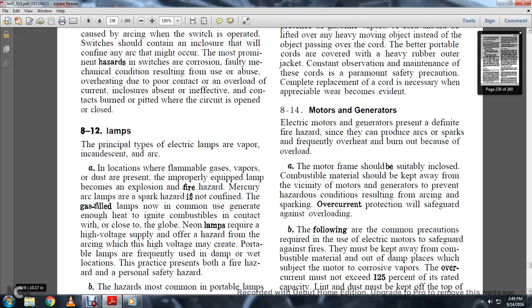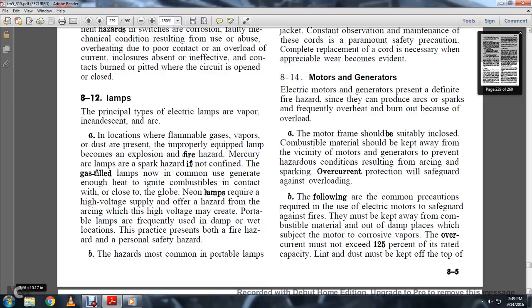8-12. Lamps. The principal types of electrical lamps are vapor, incandescent, and arc. In locations with flammable gases, vapors or dust, an improperly equipped lamp becomes an explosion or fire hazard. Mercury and arc lamps are spark hazards if not confined. The gas-filled lamps now in common use generate enough heat to ignite combustibles in contact with or close to the globe.